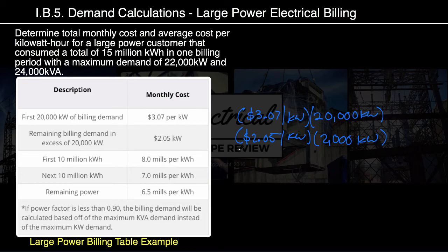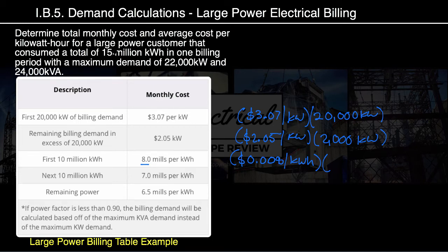Now let's look at the first tier of our energy charge: 8 mils per kilowatt hour. The quick conversion to dollars — that's the third decimal place — gives us $0.008 per kilowatt hour. For the first 10 million kilowatt hours: we've got 15 million total, which is greater than 10 million, so we write 10,000,000 kilowatt hours for this tier.